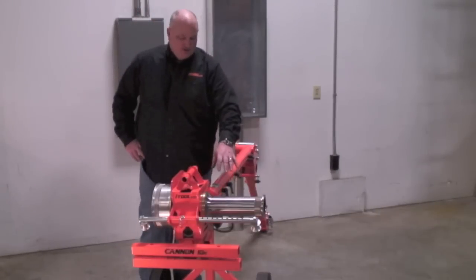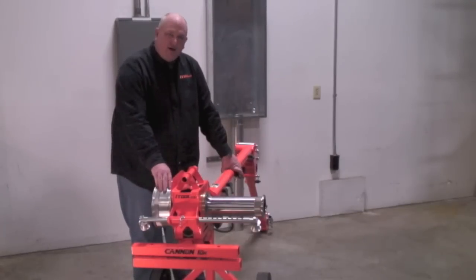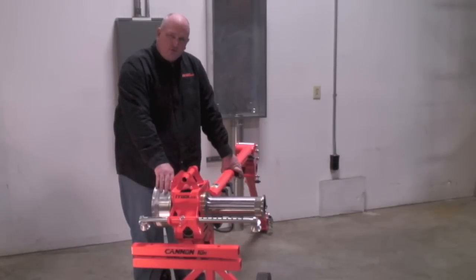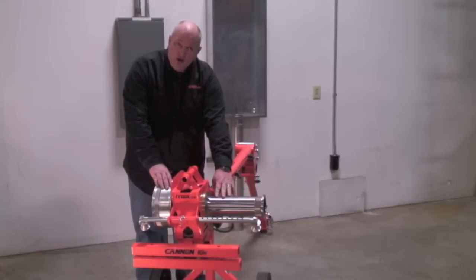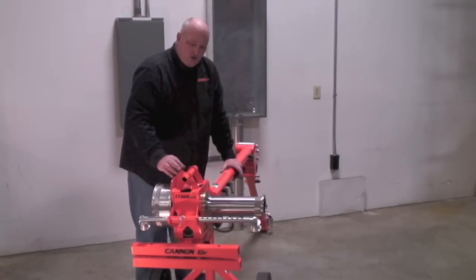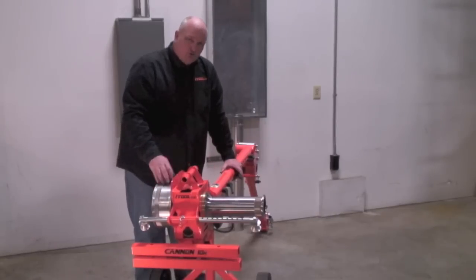Now let's talk about the dual capstands. We have 9 and 18 feet a minute on the 10,000 pound side and 20 and 40 feet a minute on the 5,000 pound side. Where that's significant for you as a contractor: if you were pulling a 500 foot run of 500 MCM with your old tugger at six feet a minute, you're looking at about 83 minutes of run time. With the Cannon here, you can simply start out on the high speed capstand for the first 400 feet because the load's not that great, then swap over to the 10,000 pound side capstand when the load gets heavier than 5,000 pounds — just swap the rope over and finish the pull. What used to take 83 minutes can now be accomplished in about 20 minutes with our dual capstand technology.